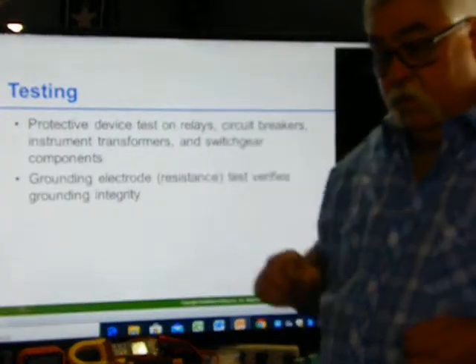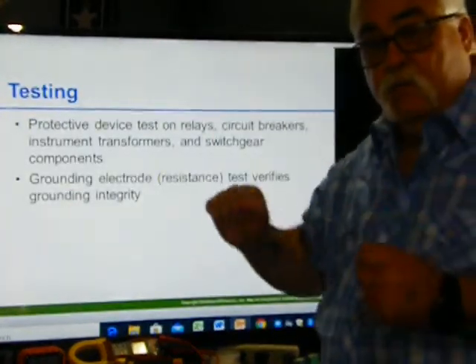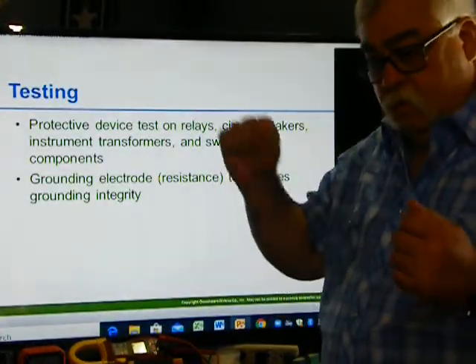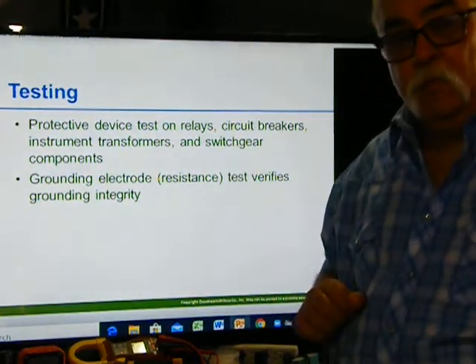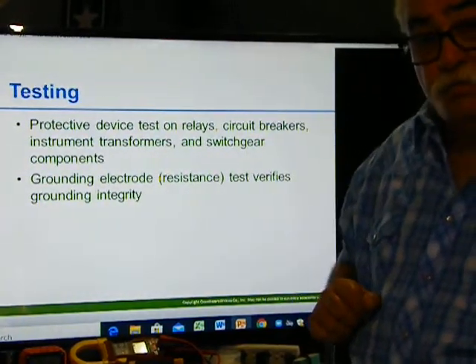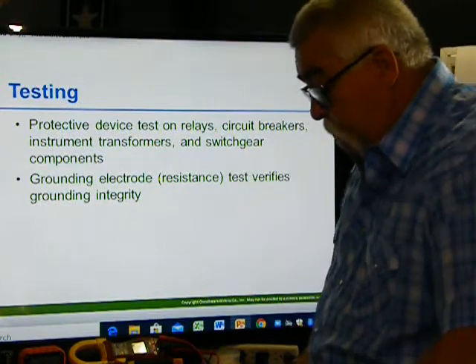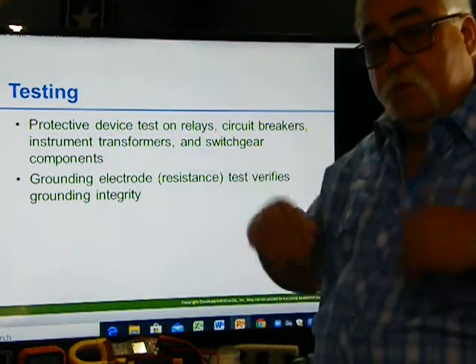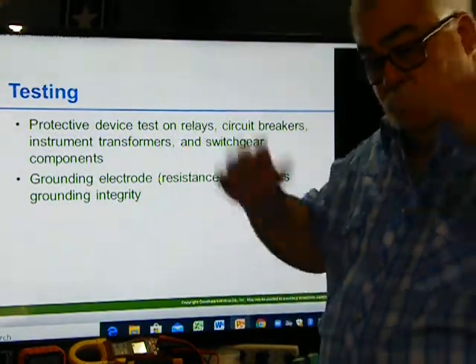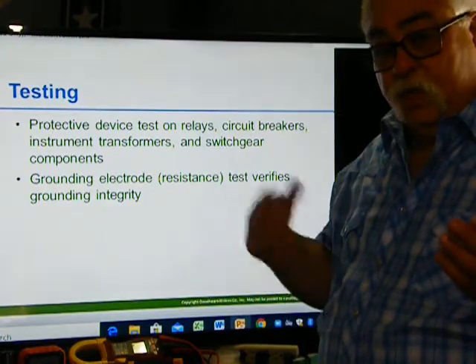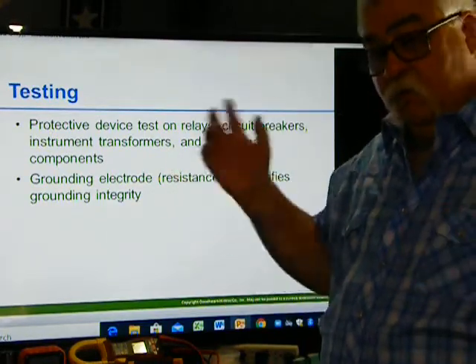And then with a torque wrench, make sure everything is torqued properly. Every bolt, make sure the bolts were torqued properly. So we did this on transformers once a year, dry type transformers. Okay, switchgears, we turn them on and off. When we turn power off, we turn them back on. After we cleaned them, we turn power off, turn them back on.